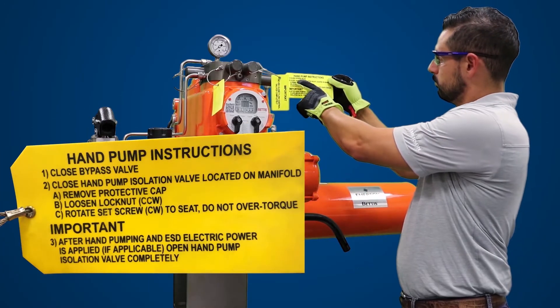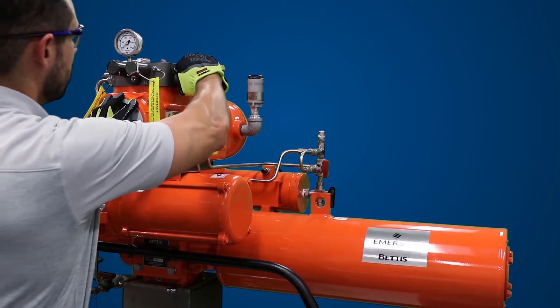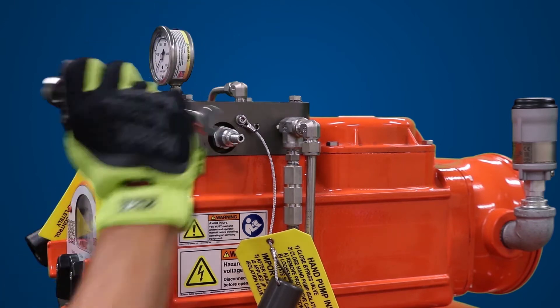Next, we want to verify the hand pump operation. Read the hand pump instructions on the yellow tag. To operate the hand pump, the hand pump isolation valve must be fully closed in the clockwise direction. If not, pressure will not build up when operating the hand pump.